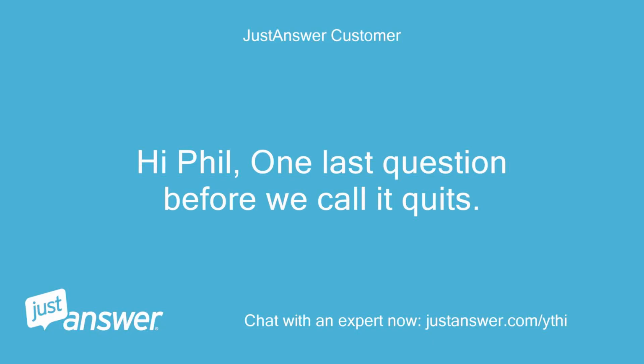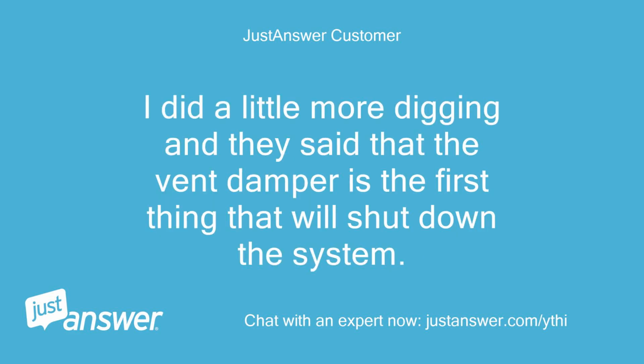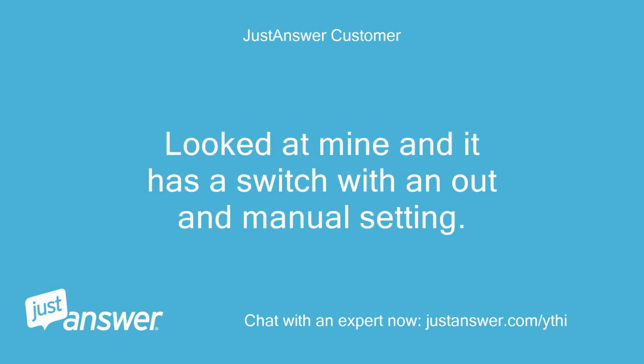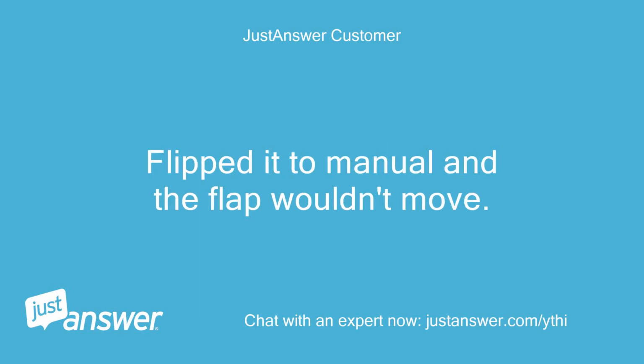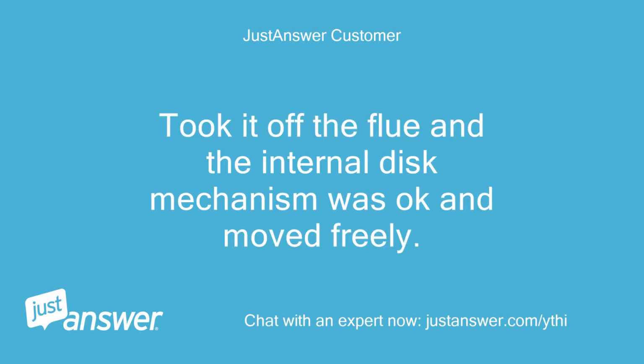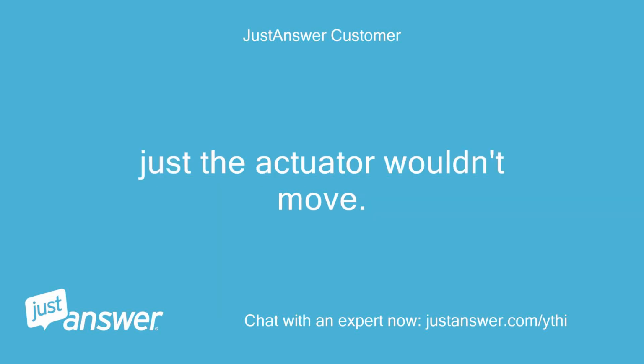Hi Phil, one last question before we call it quits. I did a little more digging and they said that the vent damper is the first thing that will shut down the system. Looked at mine and it has a switch with an out and manual setting. Flipped it to manual and the flap wouldn't move. Took it off the flue and the internal disc mechanism was okay and moved freely. Just the actuator wouldn't move.